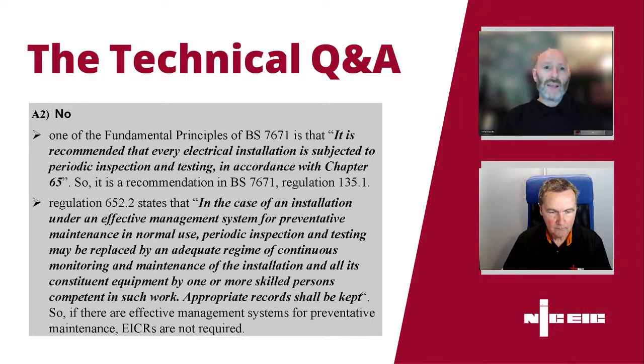So what you've got to consider is the fundamental principles within BS 7671. It recommends that every electrical installation is subjected to periodic inspection testing in accordance with Chapter 65. So it is a recommendation only to carry out that type of testing and inspection. There are further regulations to apply, depending on considerations such as whether the system has an effective preventive maintenance program in place. Then that might replace the option of periodic inspection testing, because it's being checked on a regular basis, ensuring that this work is being done by a skilled person who is competent in that scope of work.